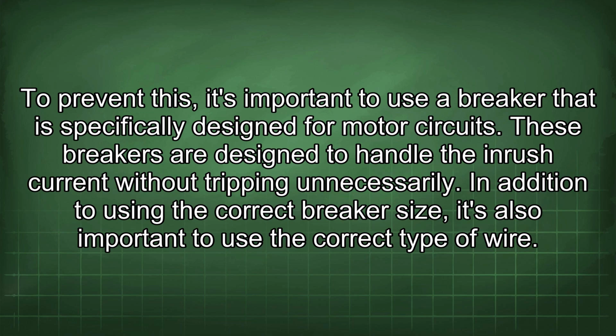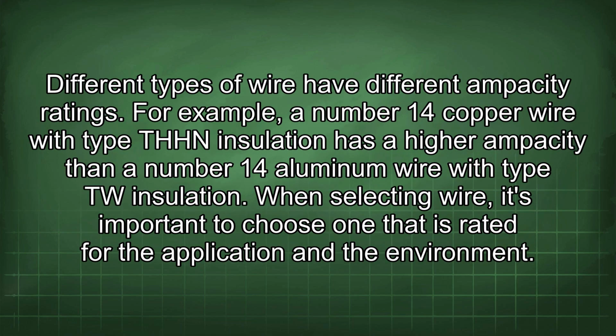In addition to using the correct breaker size, it's also important to use the correct type of wire. Different types of wire have different ampacity ratings. For example, a number 14 copper wire with type THHN insulation has a higher ampacity than a number 14 aluminum wire with type TW insulation. When selecting wire, it's important to choose one that is rated for the application and the environment.